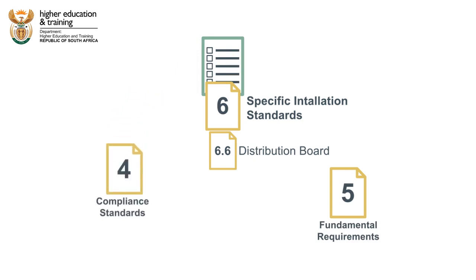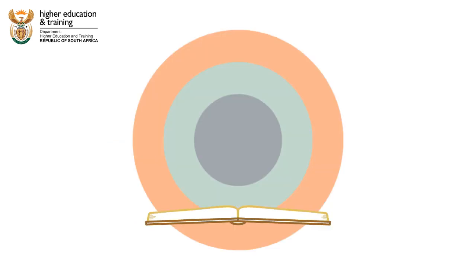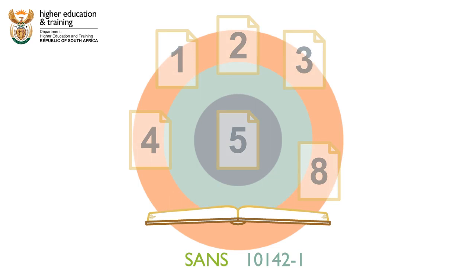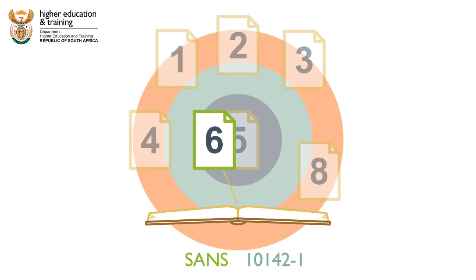You would also need to go through Clause 6.7 – Protection to make sure that the overcurrent, overload and short circuit protection in the board was compliant. From this simple example, we can see that the SANS Code 10142-1 cannot be read like a book from beginning to end. Often, it is a good idea to start with Clause 6 – Installation Requirements or Clause 7 – Special Installations and Locations, and then to read out from there.